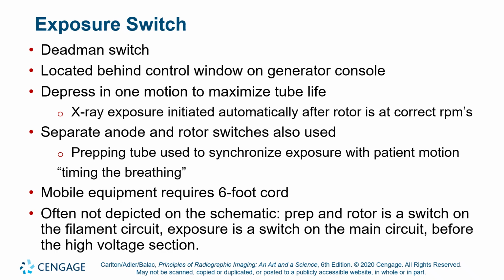So, yes, it does extend tube life to mash it all down in one go. But there's a reason it's a two-phase switch. You're giving breathing instructions or final instructions to your patient. At the very least, hold still. And then what do you suppose that window is for? Because lead glass is expensive. Oh, yeah, you're supposed to look through it and confirm that your patient is following your instructions. If they're not, well, then get your finger off the prep button and go back in there and explain it. But if you press it all down in one motion, are you going to catch it in time?